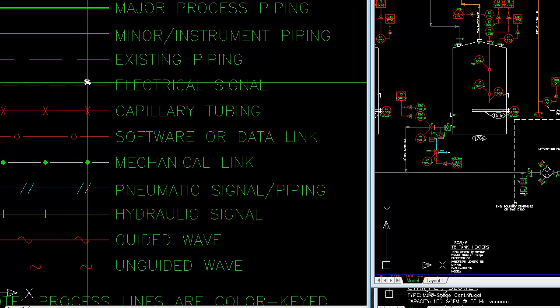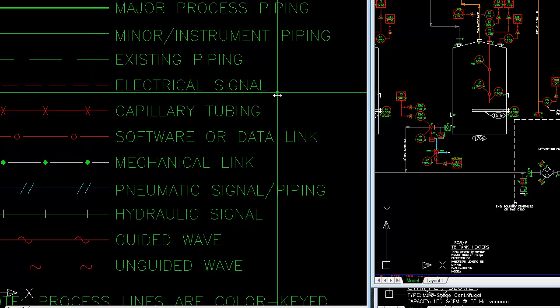The use of a dash line, I tend to use it for piping that's existing, and it's helpful to show if you are making an add-on, to show existing piping is dashed, so that contractors and other engineers working on the project understand that that line is actually existing and you're tying into it.